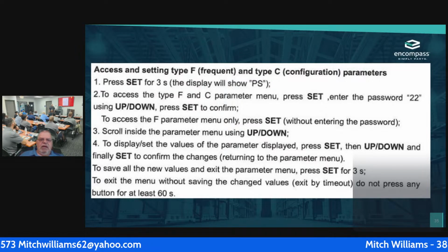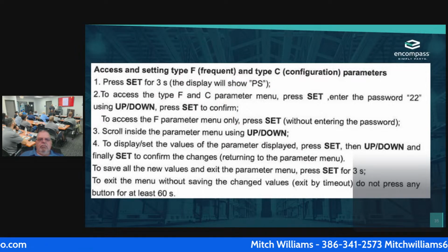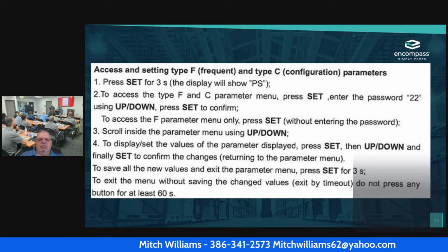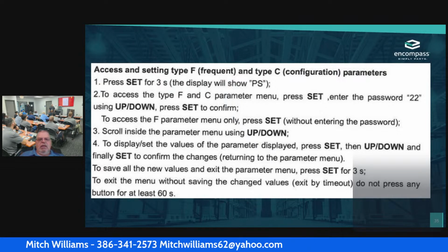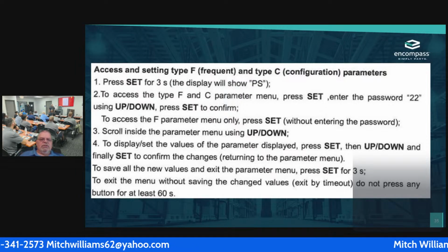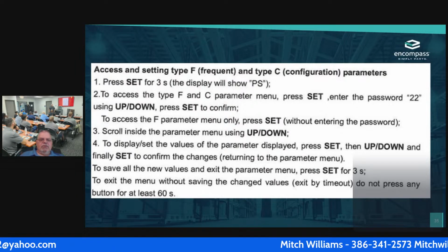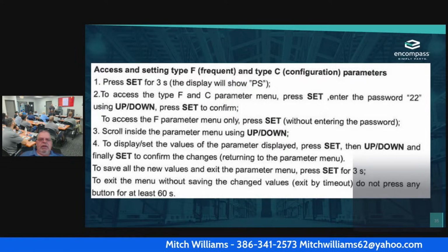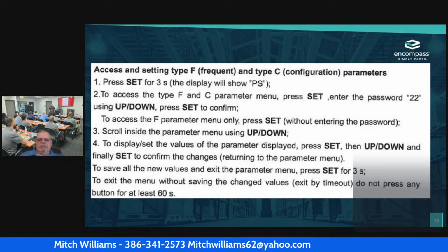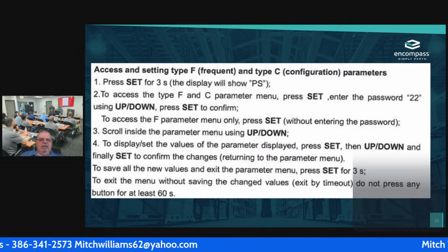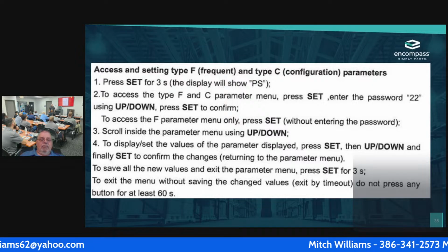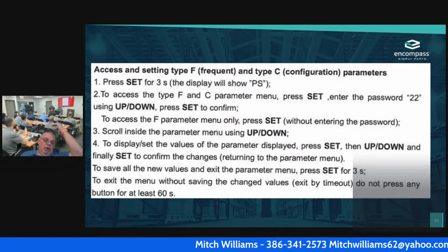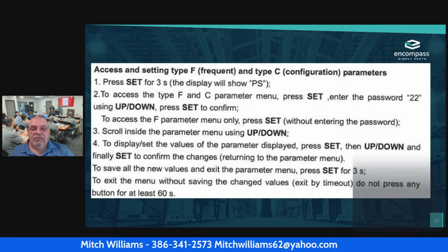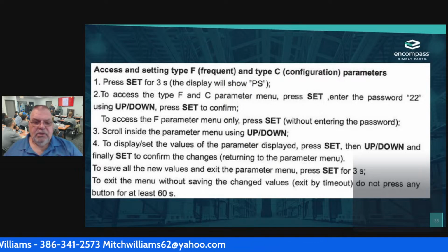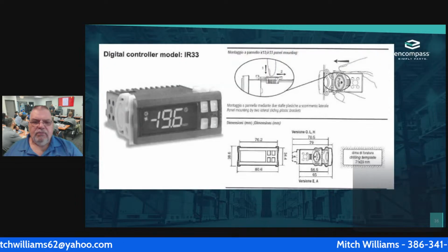To access the F parameter menu only, press set without entering the password, and that will automatically enter my F parameter. Scroll inside the parameter by using the up and down buttons to display the set values of the parameter. Press set, then up and down, and finally set to confirm any of the changes. This is on the different controller. To exit the menu without saving the changes, just press the off one more time.